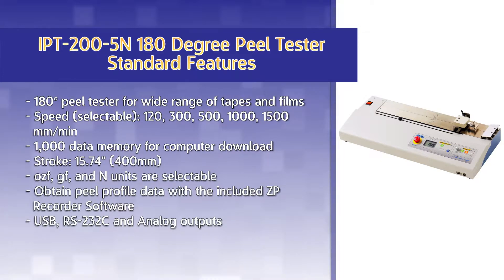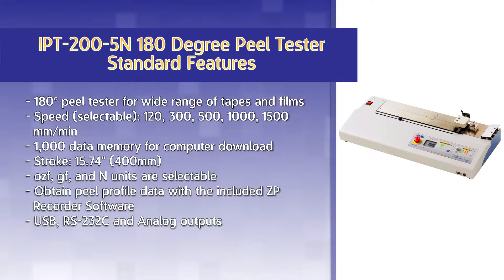The IPT has a 1000 data internal memory which can also be downloaded to a computer. The tester features a large working area with a stroke of 15.74 inches or 400 mm. Ounces force, grams force, and newtons are the three units selectable on the unit. Obtain peel profile data with the included ZP Recorder software.